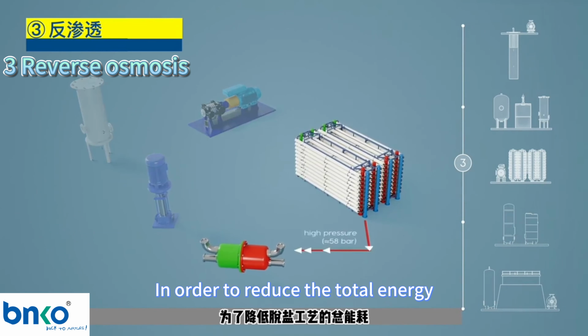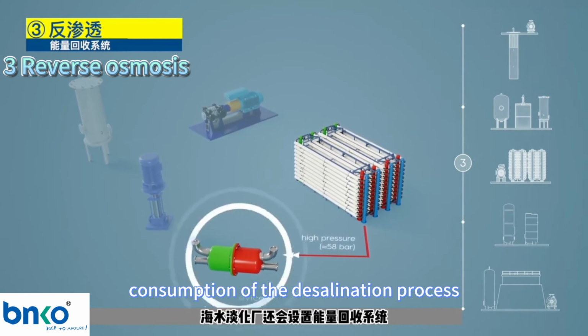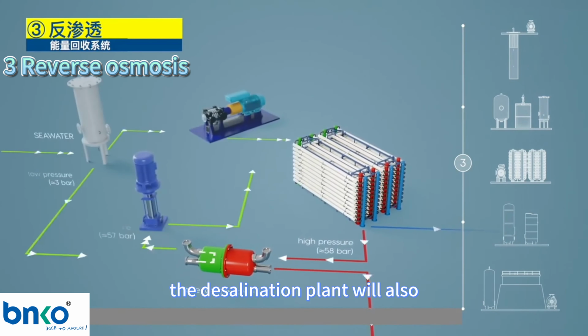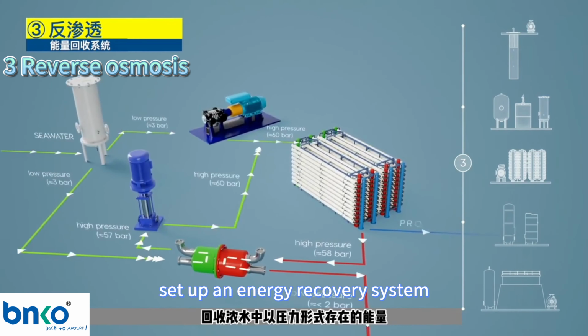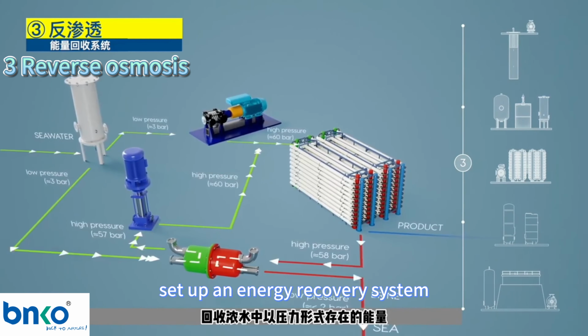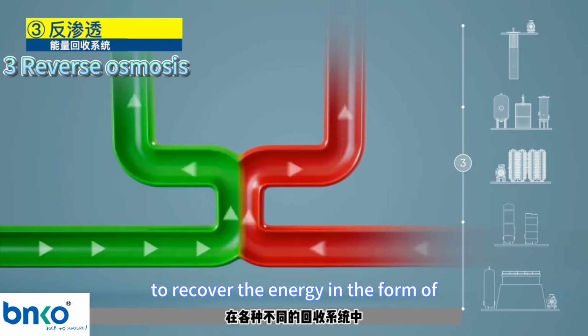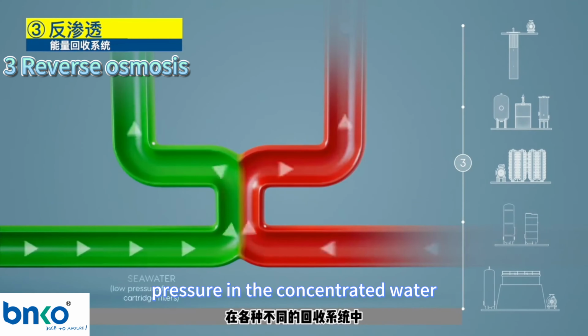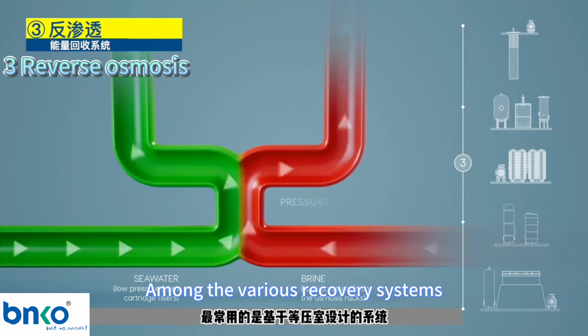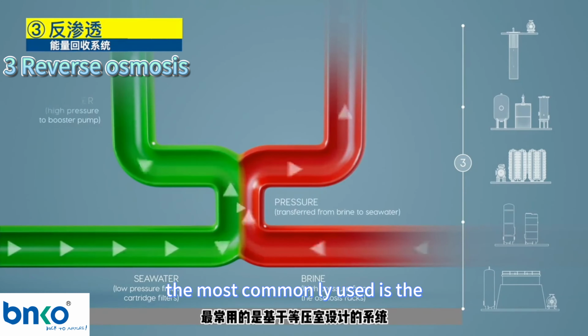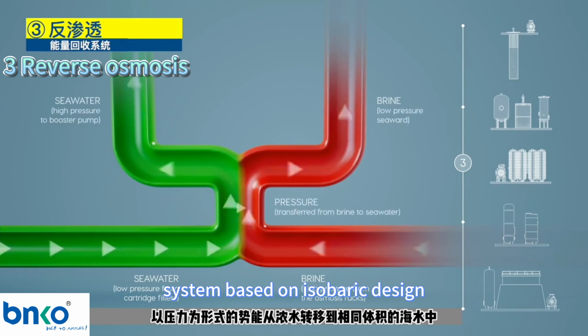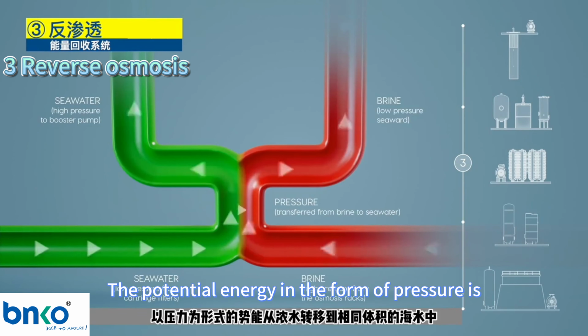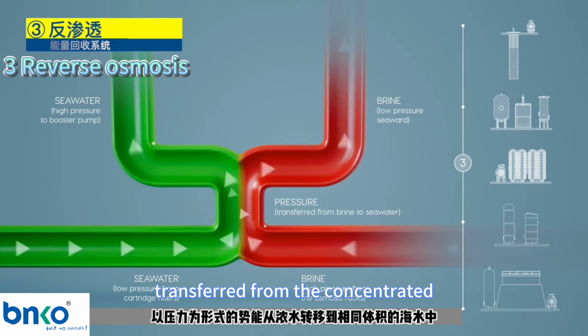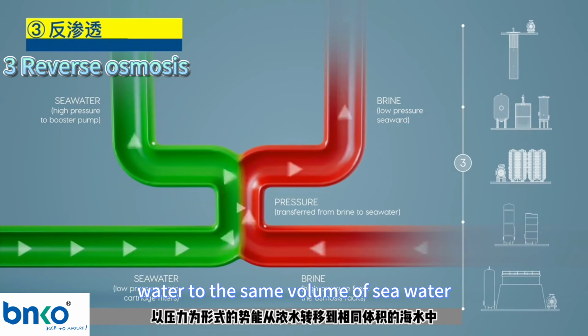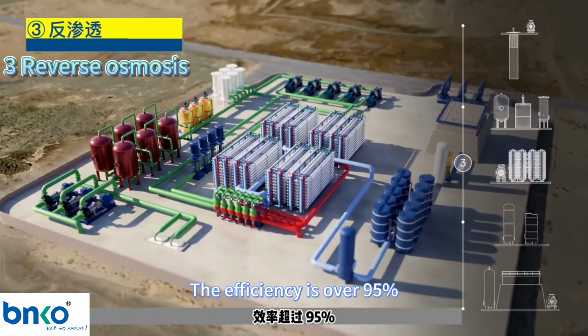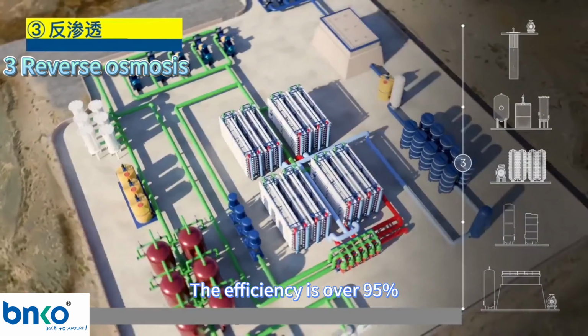In order to reduce the total energy consumption of the desalination process, the desalination plant will also set up an energy recovery system to recover the energy in the form of pressure in the concentrated water. Among the various recovery systems, the most commonly used is the system based on the isobaric design. The potential energy in the form of pressure is transferred from the concentrated water to the same volume of seawater. The efficiency is over 95%.